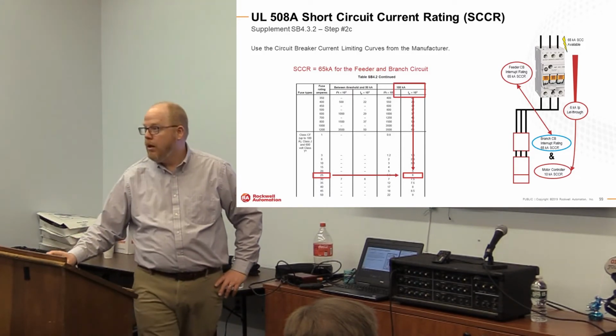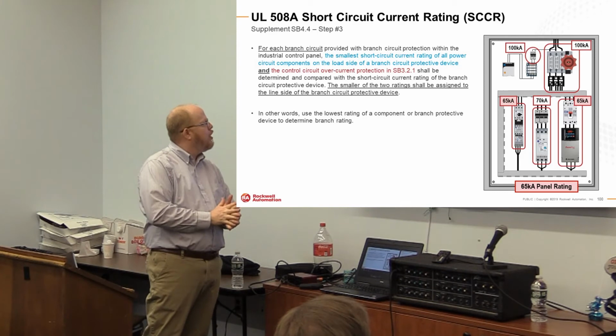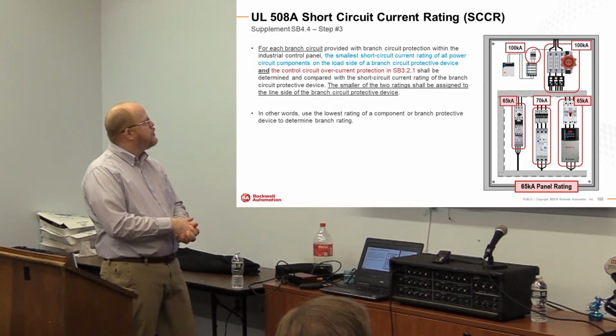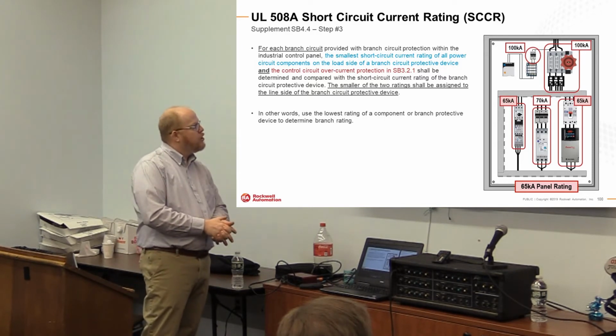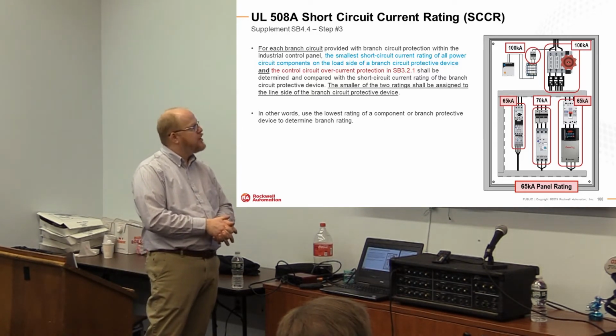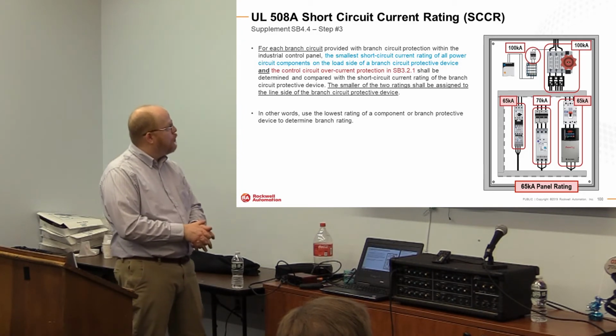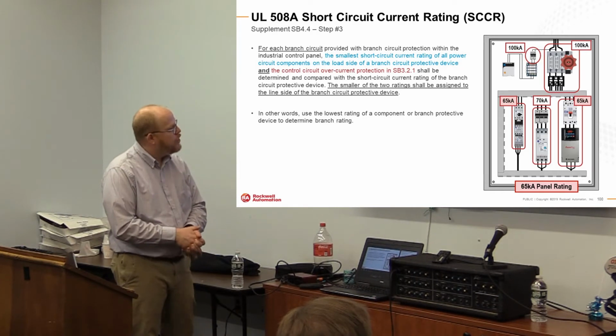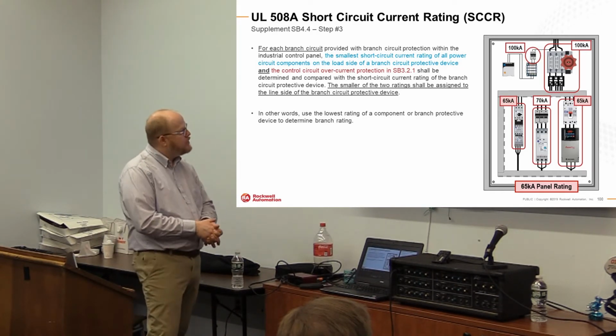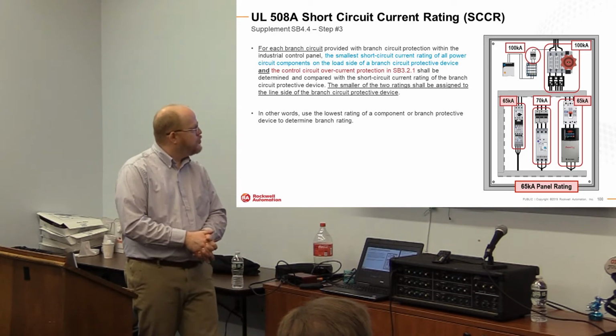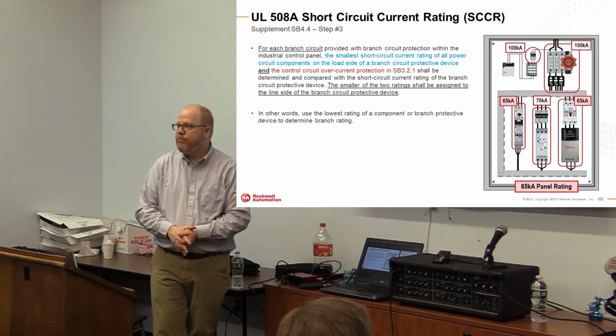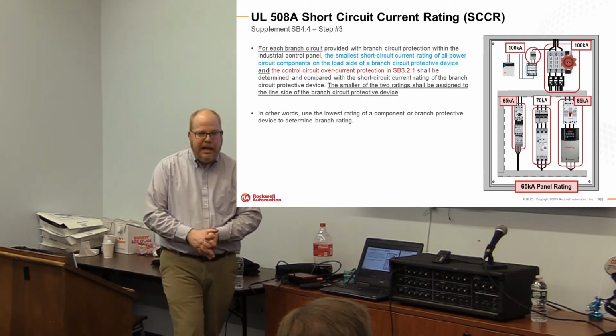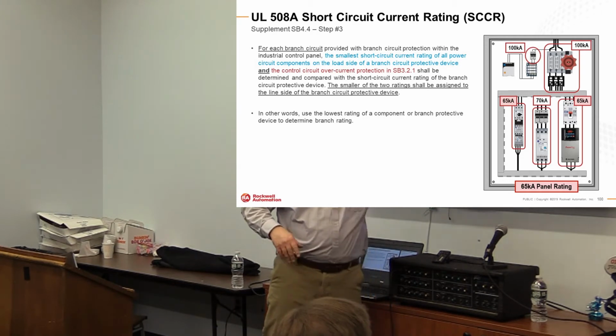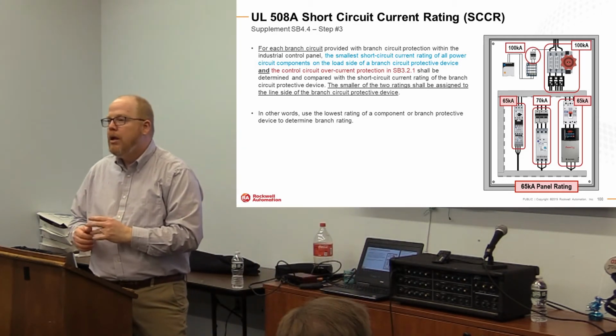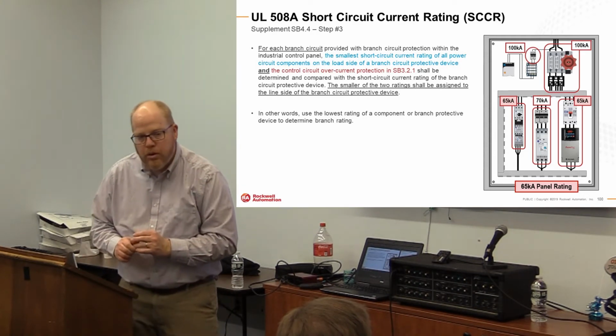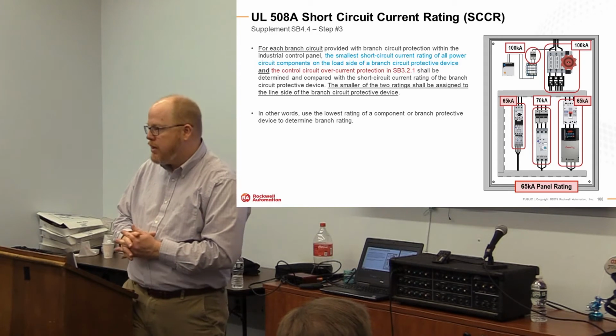Okay? So for example, and again, here's another long run-on sentence, step 3. For each branch, the smallest short circuit current rating of all power components on the load side of the branch protected device and the control circuit overprotection shall be determined and compared to the short circuit current rating of the branch circuit protective device. The smaller shall be assigned to the line side of the branch protected device. In other words, use the lowest rating of a component or branch protected device. The other thing it's saying is that power supplies and fuses, in the corner there, are exempt from this application. You carry the calculation up to the fuses and or breakers that are protecting the transformer.